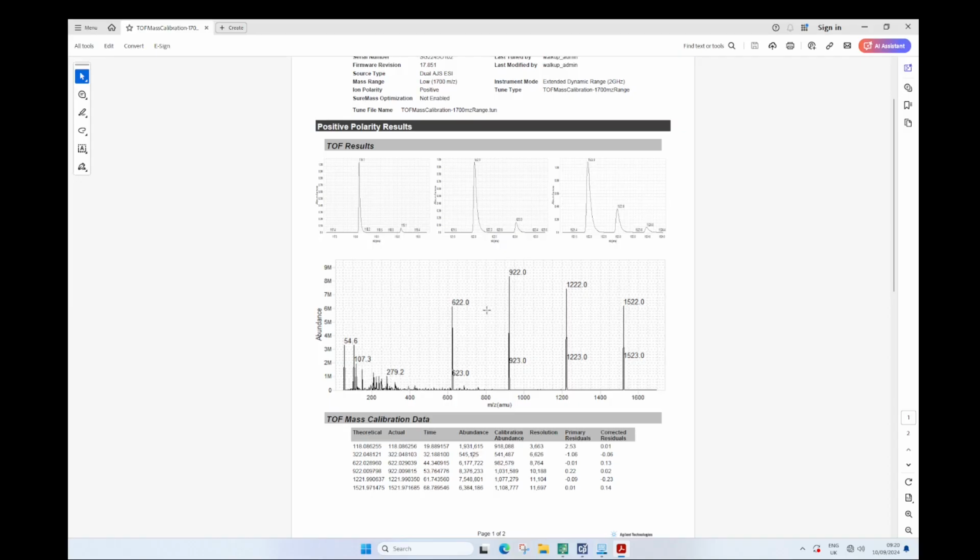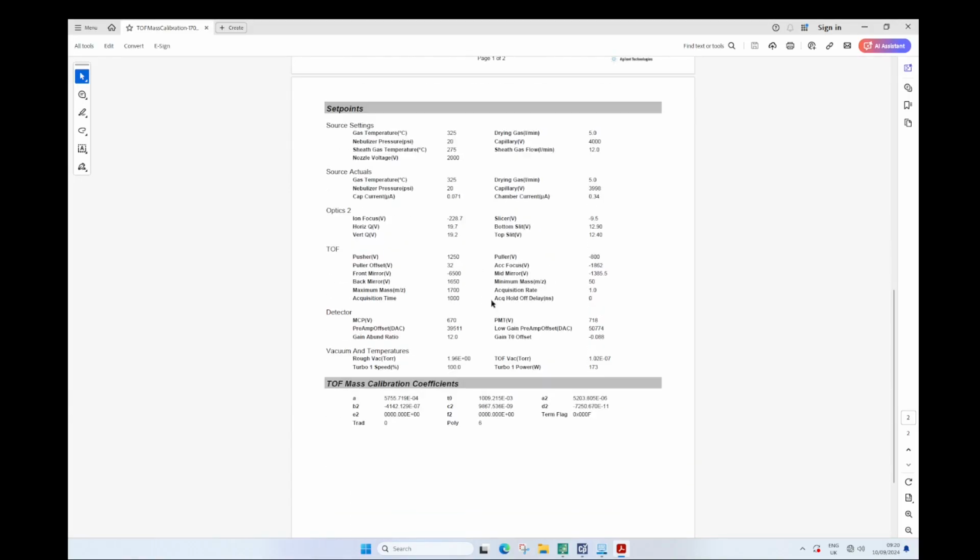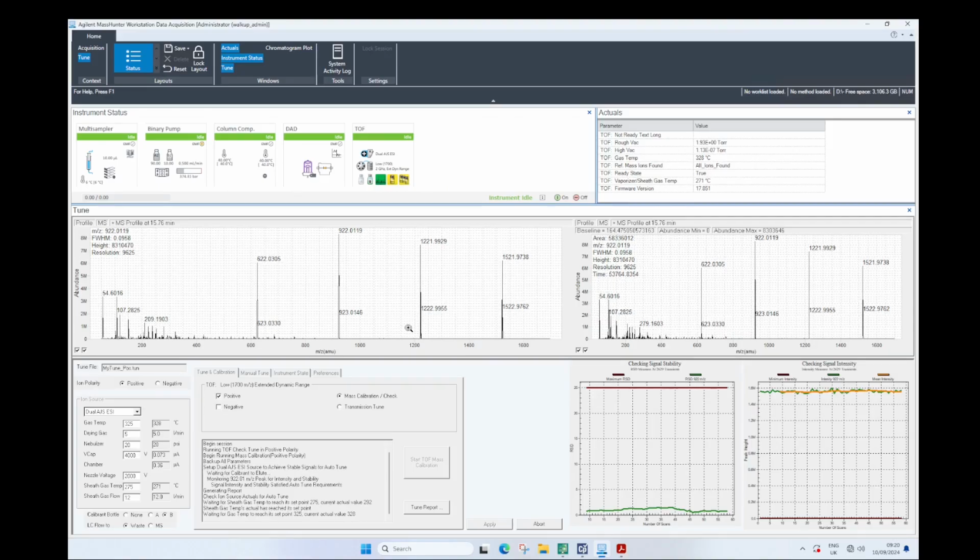Some other parameters you might want to evaluate on the day you get handed an instrument are the vacuum and the rough vacuum conditions. Let's say the system has been cleaned, these might take a while for the moisture to dissipate from the surfaces, and it's useful to keep an eye on those parameters.